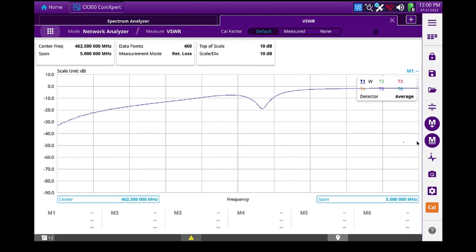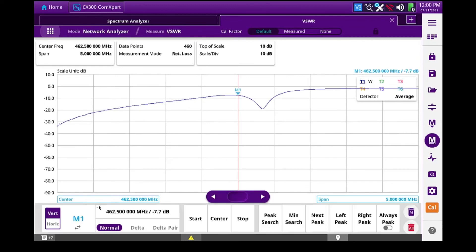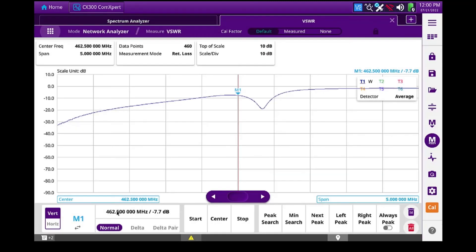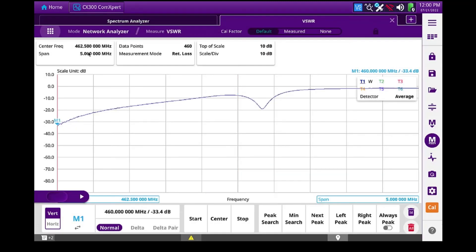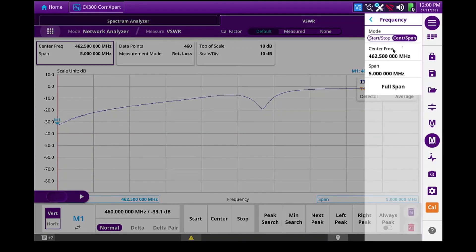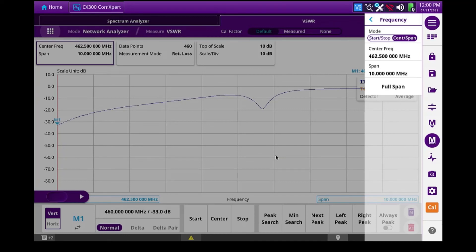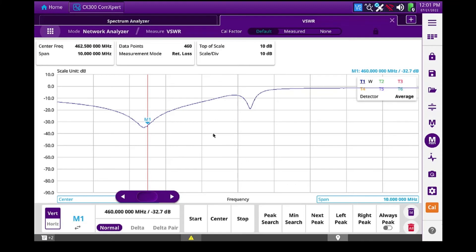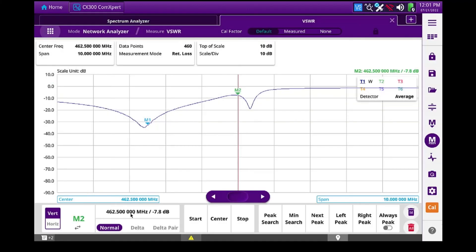Let's again turn on some markers. 460 megahertz. Span I didn't set right. 10 megahertz. And let's set marker 2 to 465 megahertz.